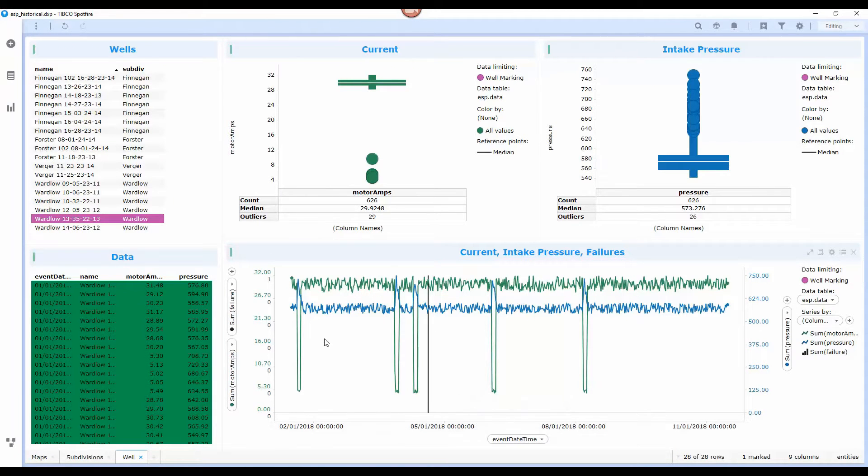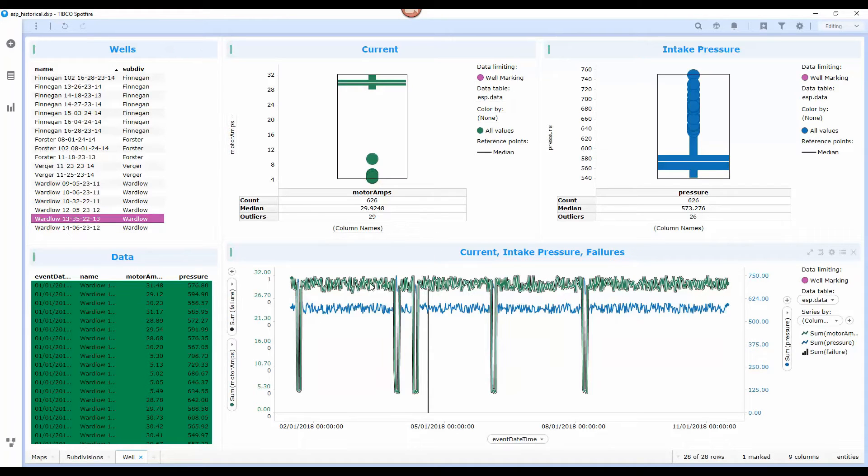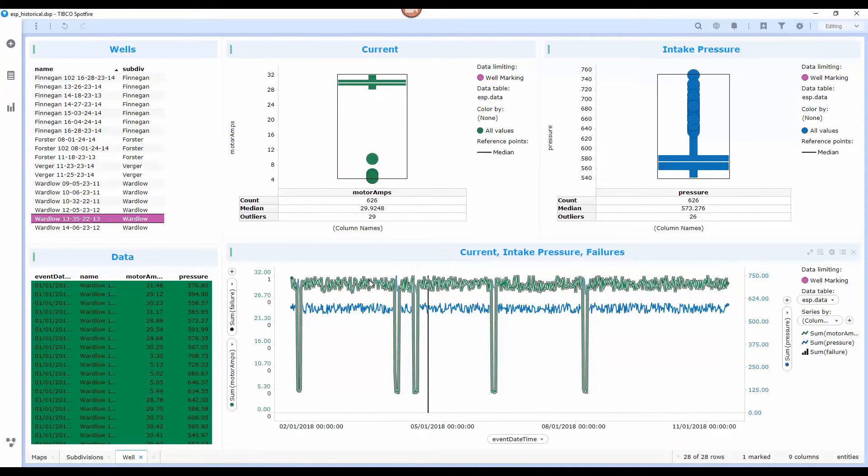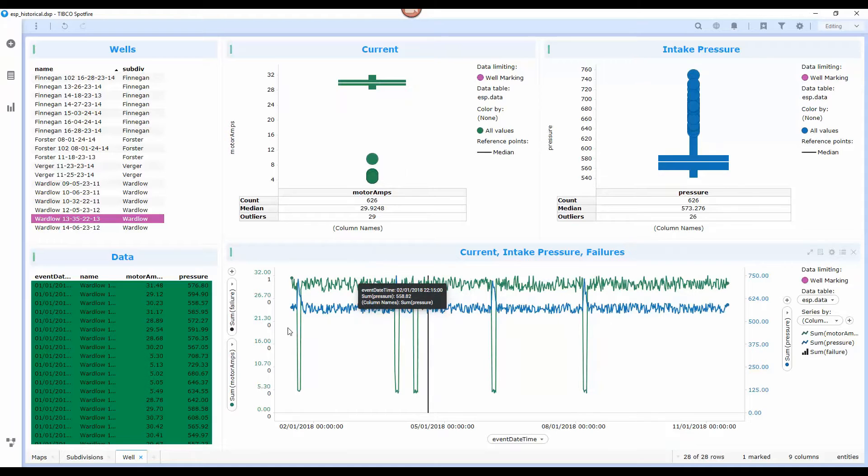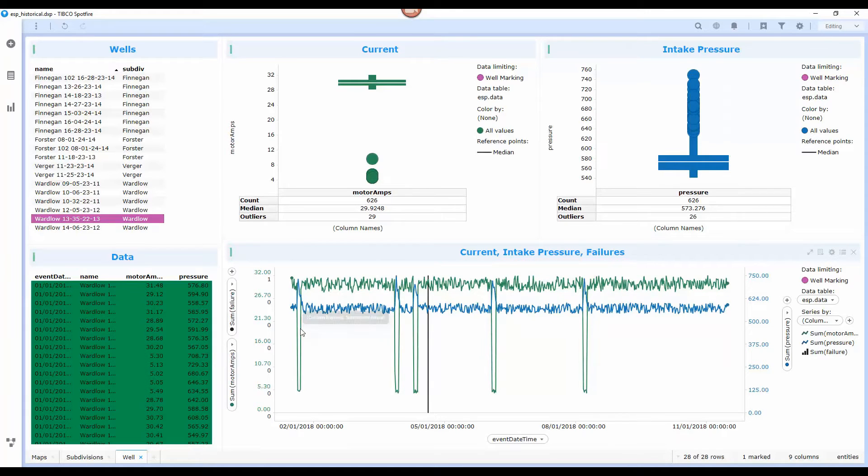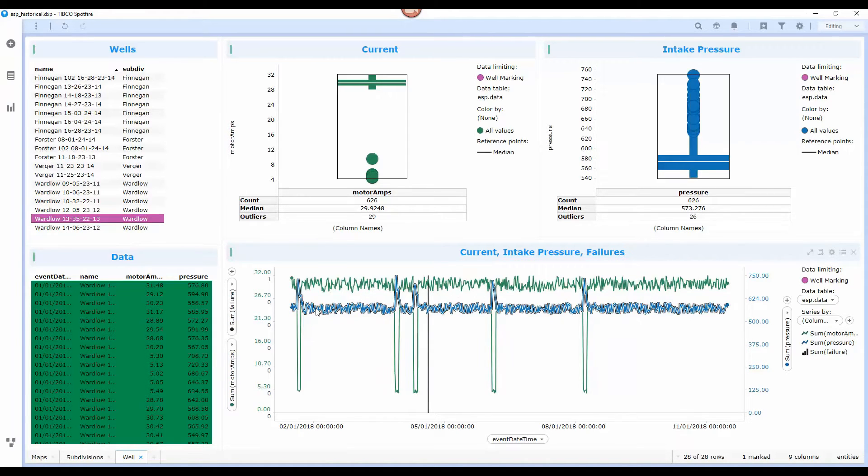So you can see here we have one particular well selected. We've got the motor amps in green and the intake pressure in blue and you can see that there's a pattern occurring where the motor amps is dropping and the pressure is rising at the same time followed by a failure.